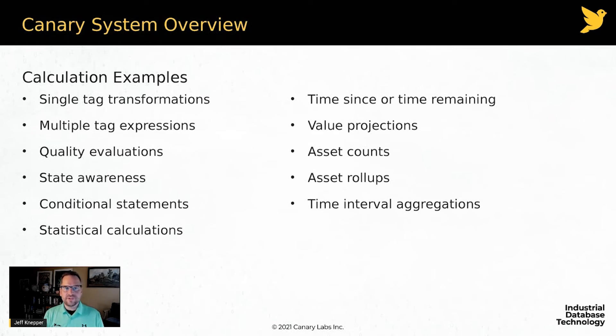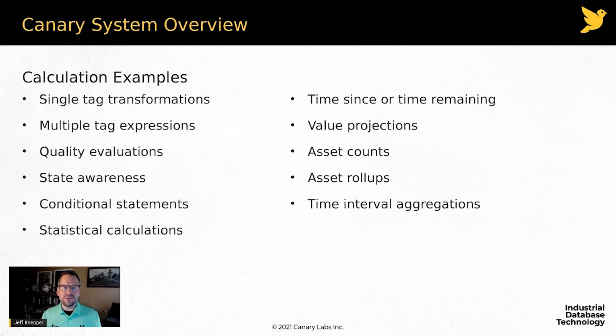Let's talk about some examples of these calculations. Something as simple as a single-tag transformation: a value is in Celsius and I want to convert it to Fahrenheit. Or a multiple-tag expression: three pumps, three flows — let's output an average flow tag. We can also do quality evaluations: if data quality is good, take this action; if bad, take this action. In the last hour, what percentage of my data quality was good?